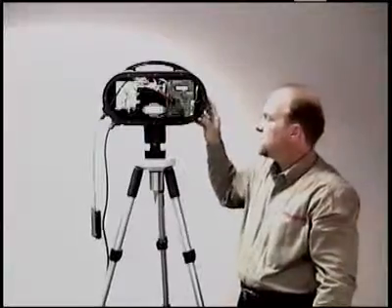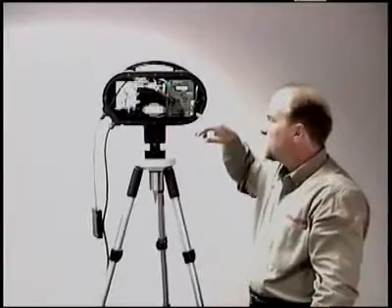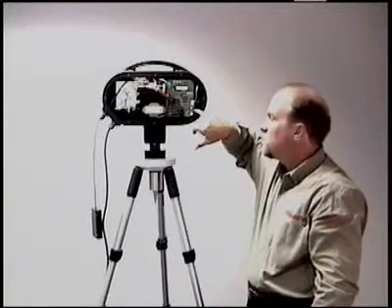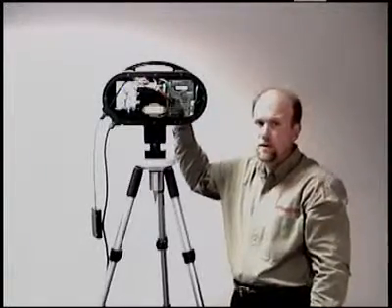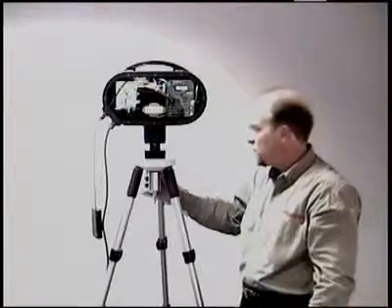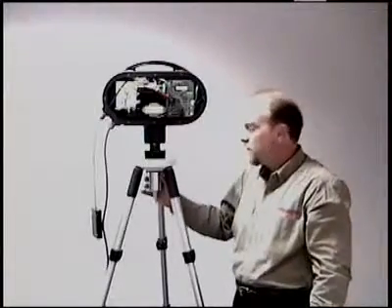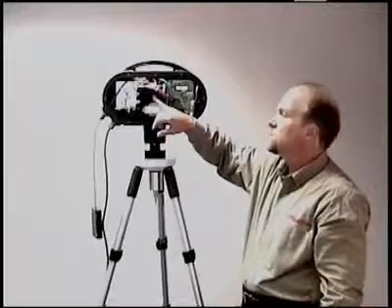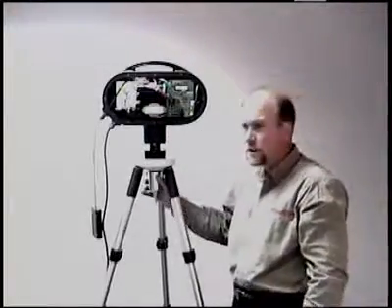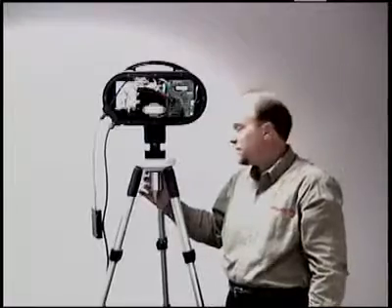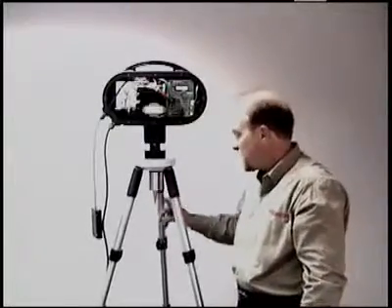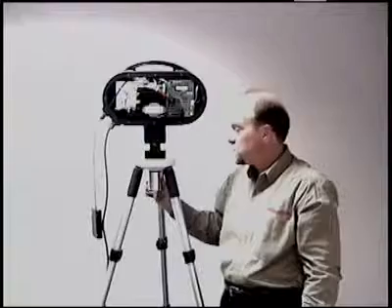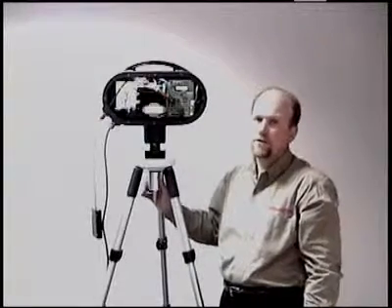We are measuring the amount of cable released with an optical encoder and a pulse wheel which pulses at about 80 times per foot. This pulse wheel is directly connected to a timing pulley. As soon as this sensor probe reaches the material surface, information is transmitted, pulses are momentarily stopped, and the microcontroller alerts the motor to immediately pull this Bob back to the neutral position at the top of the vessel. We are measuring the pulses as we go down and on the retract, comparing the two to assure that this Bob always makes it back to the top.